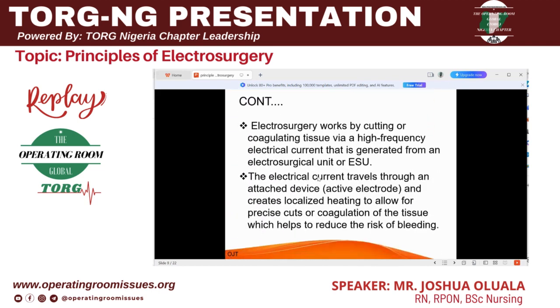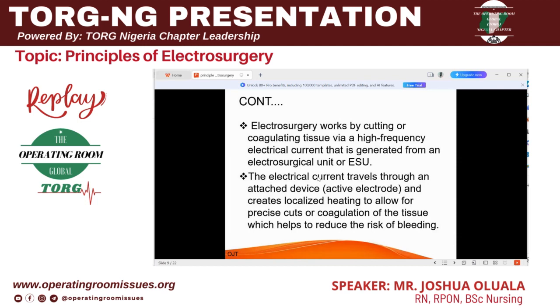Then also, electrosurgery works by cutting or coagulating tissue via a high-frequency electric current that I've talked about, that is generated from the electrosurgical unit, or ESU. The electrical current travels through an attached device. Now, this is the case in monopolar. The electrical current travels through an attached device, we call it the active electrode. Of course, that's your diathermy pencil and all those things, and creates localized heating to allow for precise cuts or coagulation of the tissue, which helps to reduce the risk of bleeding. So the desired effect, the aim of using this diathermy, is actually to prevent bleeding. As we all know, when there is excessive bleeding, of course, the surgical site will be obstructed and a lot of things can actually go wrong.